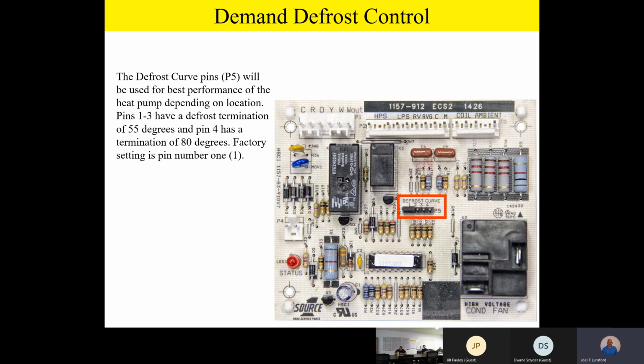Now, pins 1 through 3 have a defrost termination of 55 degrees. By the way, they're going to be set somewhere from the factory, and we recommend that factory setting. However, we do give you an auxiliary pin number 4, and that pin number 4 jumper is a termination of 80 degrees. And so you'd have to have a pretty special application to where you'd want to have an 80-degree termination point. I don't know, maybe if you were in Arizona or something like that, the high mountains of Arizona where it's super, super dry and you don't build a lot of ice up, and you want a little bit more of a termination point.